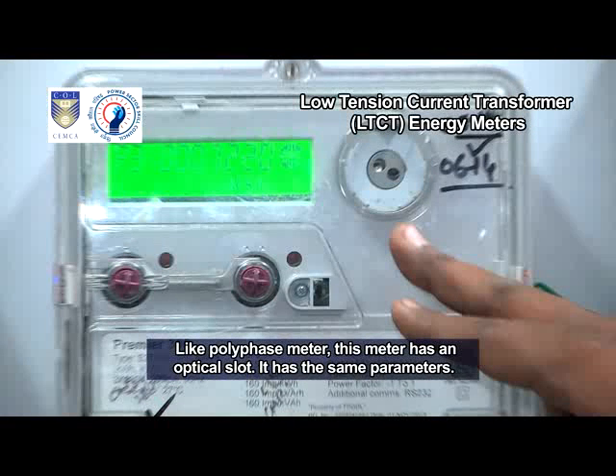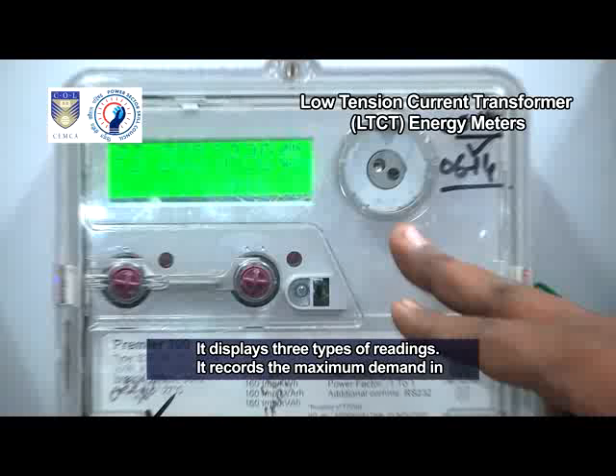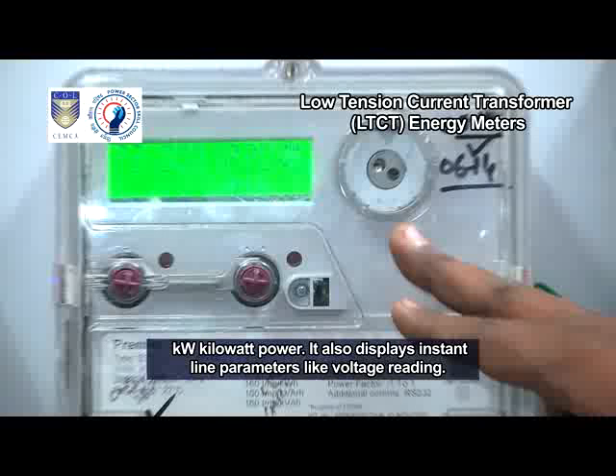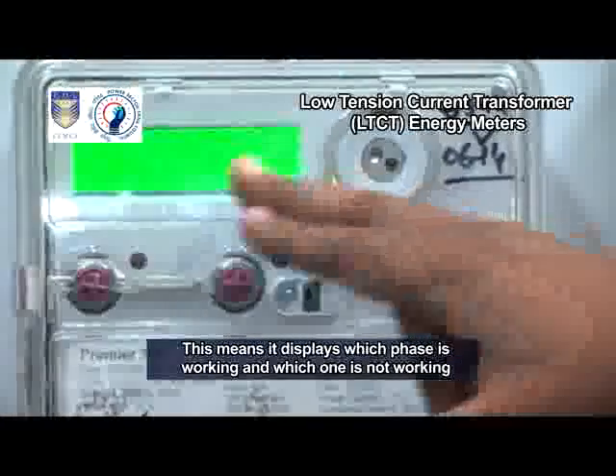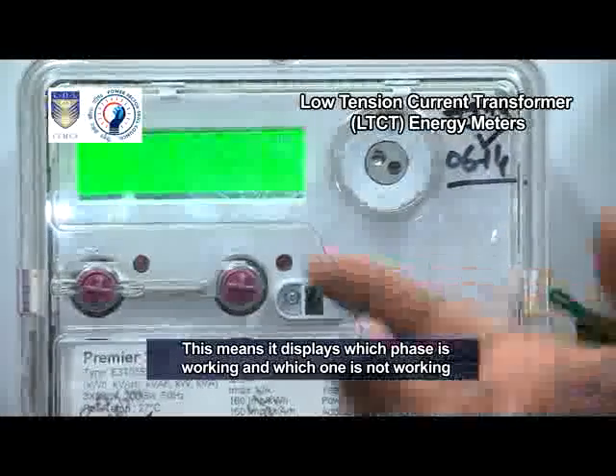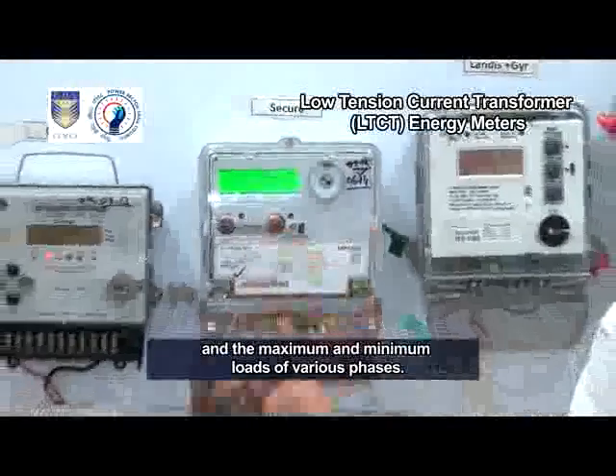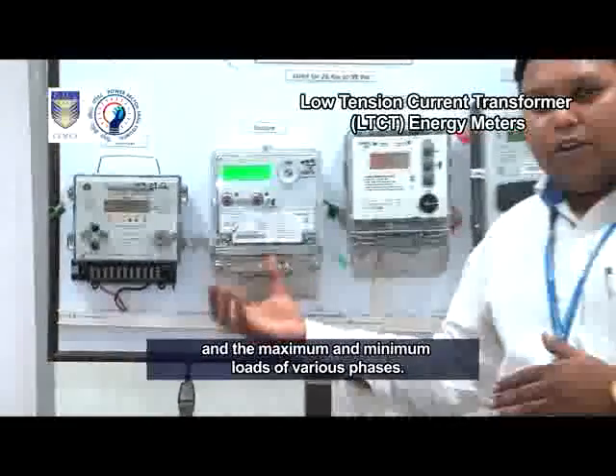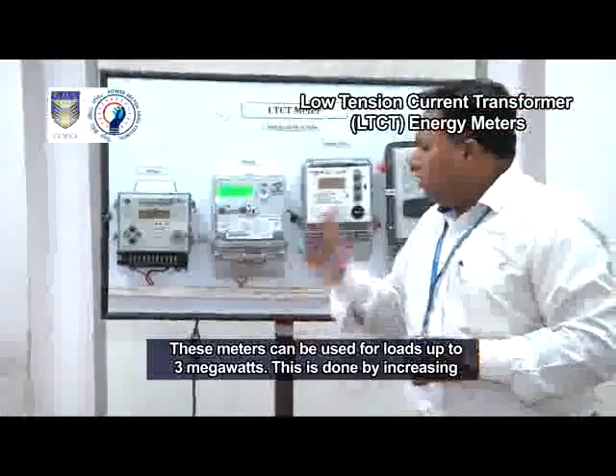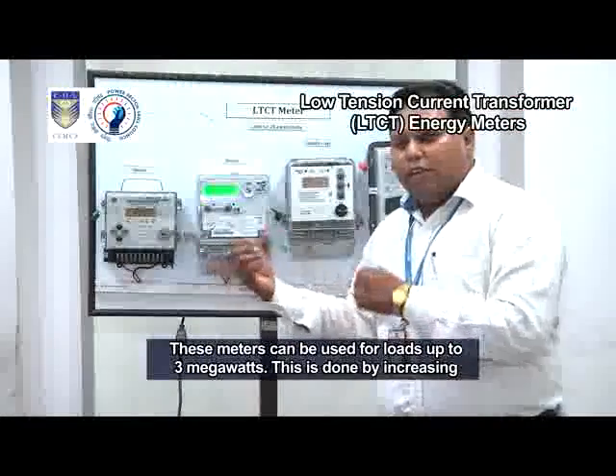Like a polyphase meter, this meter has an optical slot. It has the same parameters. It displays 3 types of readings. It records the maximum demand in kW, kilowatt power. It also displays instant line parameters like voltage reading. This means it displays which phase is working and which one is not working, and the maximum and minimum loads of various phases. These meters can be used for loads up to 3 megawatts.